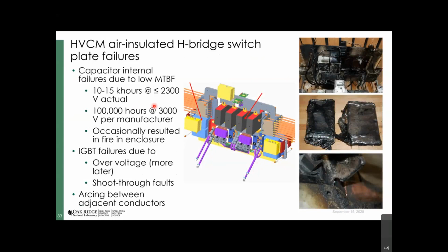One of the things we encountered was that the capacitors were not living up to the manufacturer's expectations. The specification was for them to last 100,000 hours at 3,000 volts of operation, but in our experience, they would only last an order of magnitude less at almost 700 volts lower voltage. So that was not good.